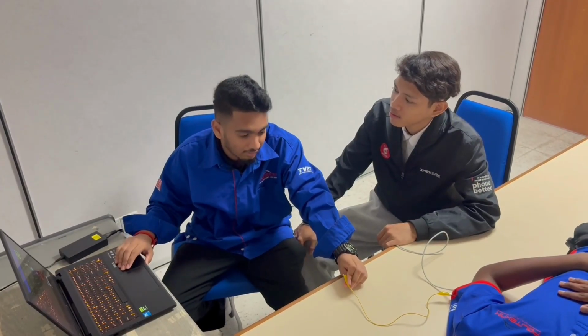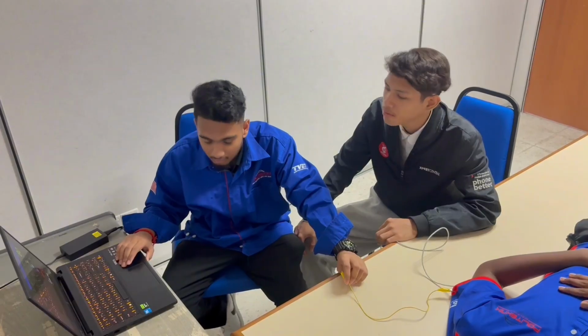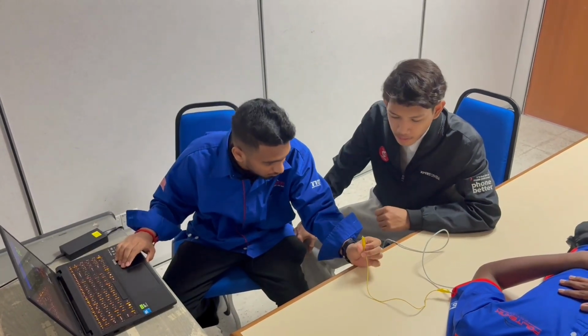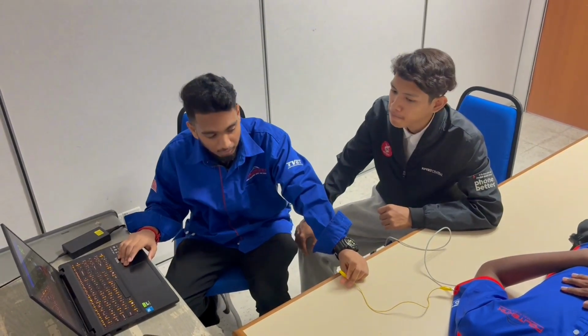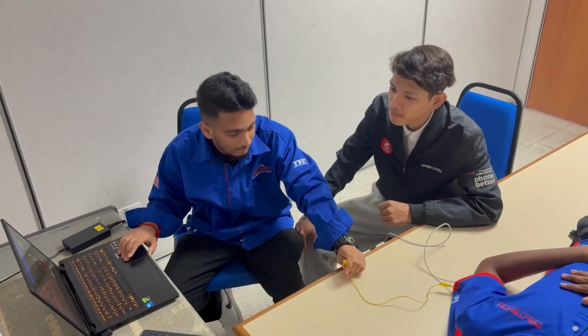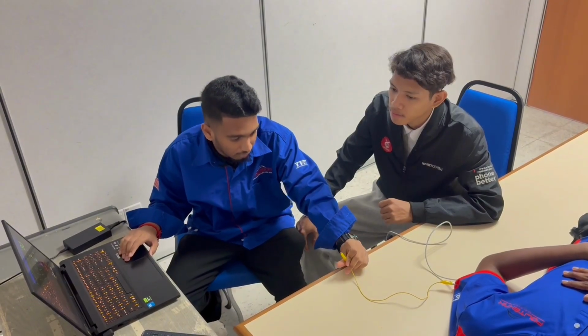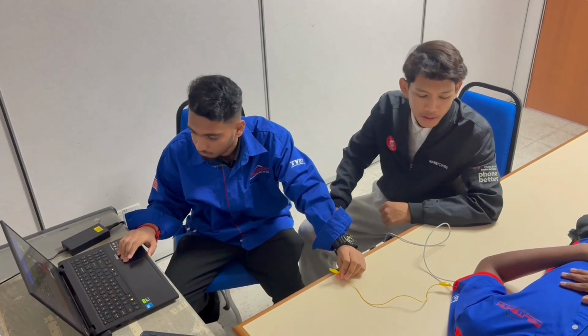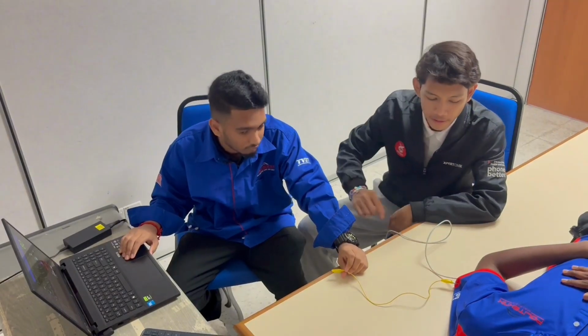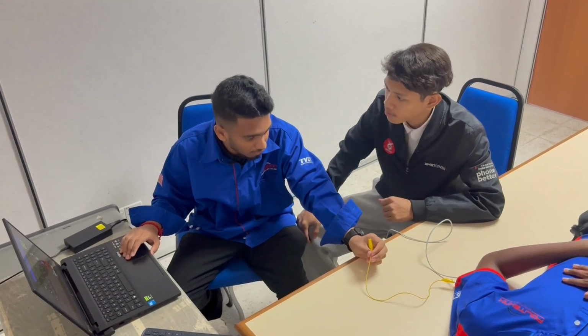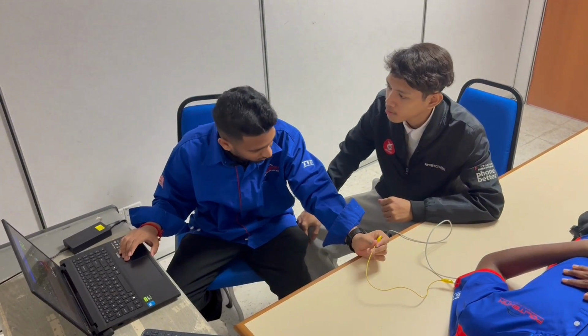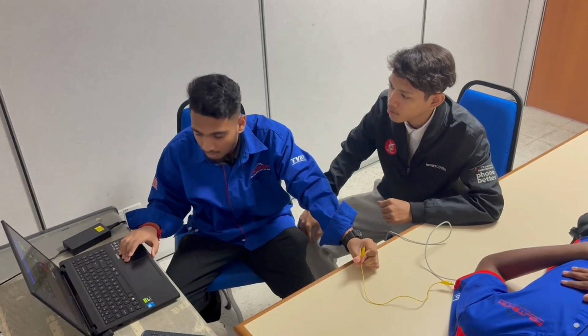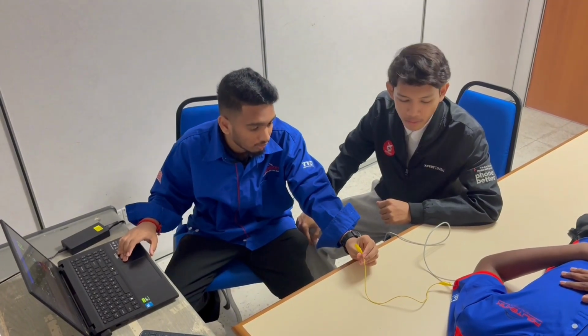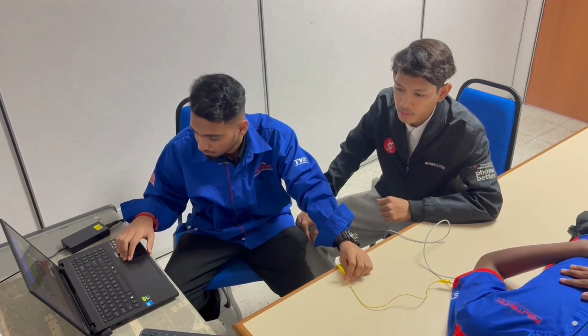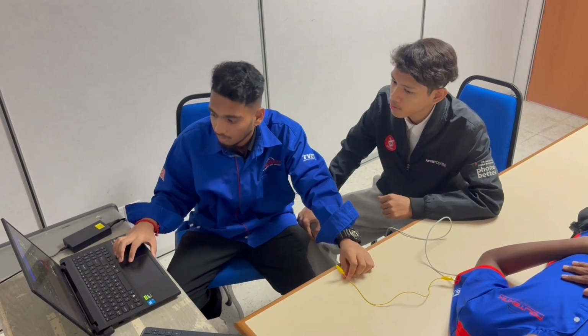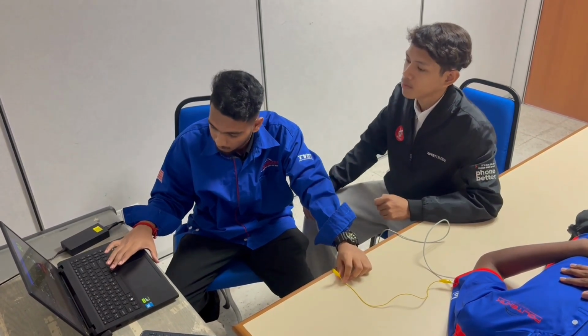First, I checked the blood pressure cuff and the tubing for any visible damage. The cuff doesn't appear damaged, and I don't see any leaks or cracks on the tubing. Okay, could the problem be caused by the cuff? It's possible, but the cuff looks fine. I also checked the connection between the cuff and the monitor. The connection is secure as well.